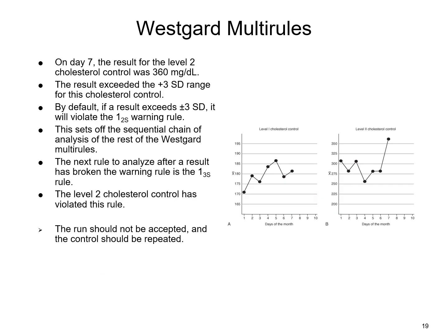On day 7, of course, we want to get a little color code going on here where we determine our standard deviations. So we know that this is our 2 standard deviation line, and then of course our 3 standard deviation line. And look at that, we've got it all the way outside of our 3 standard deviation line.